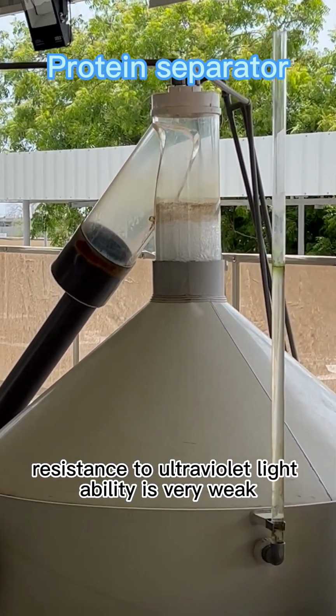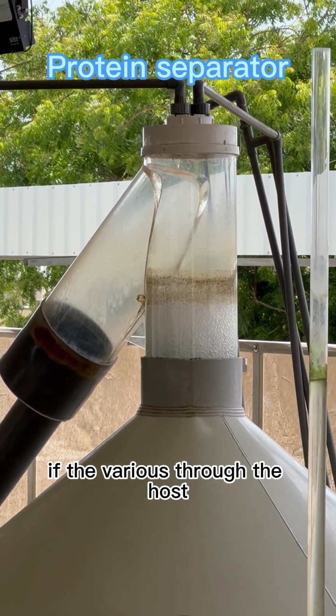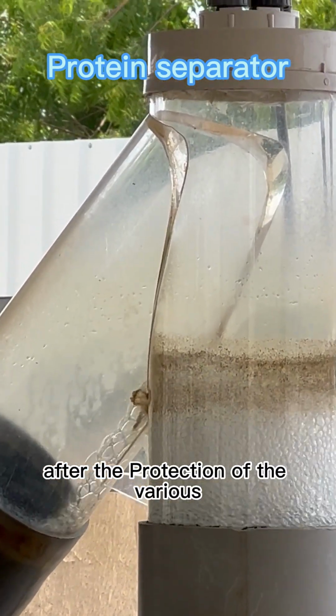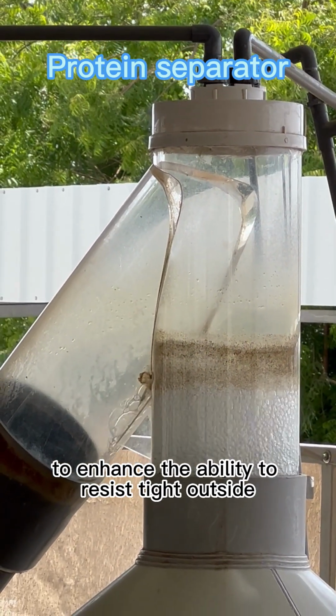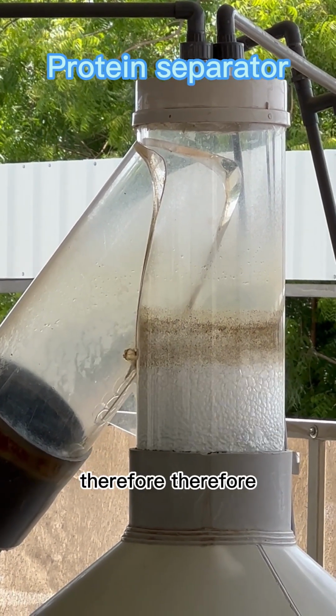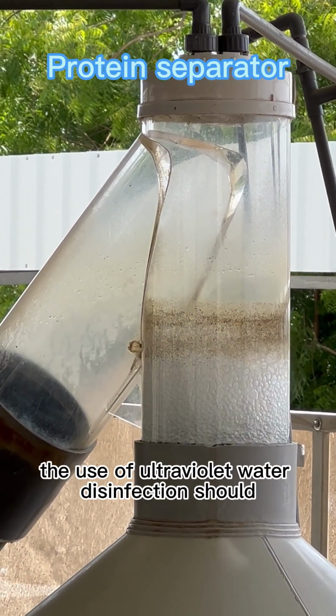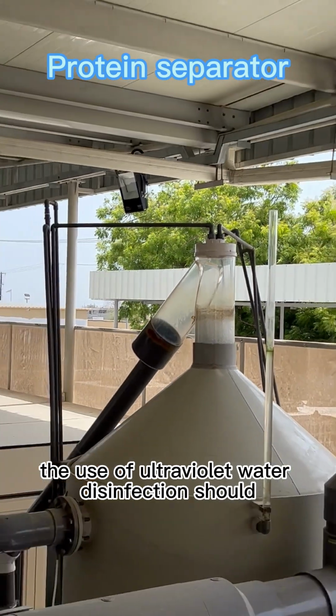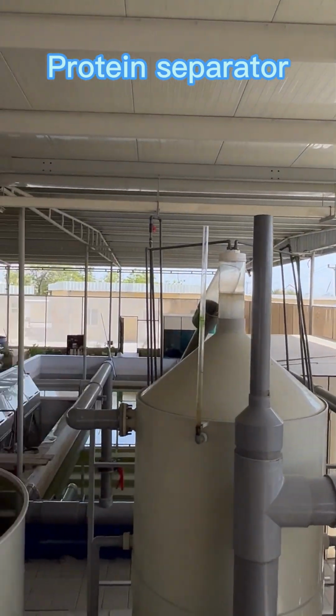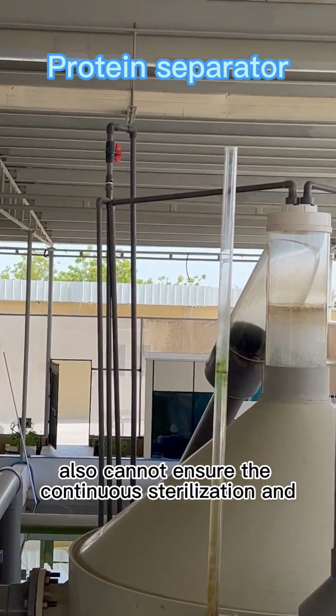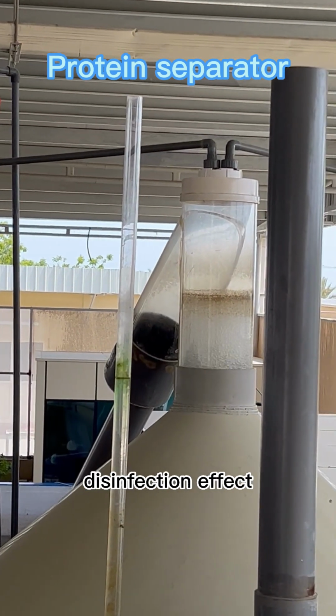The virus itself has very weak resistance to ultraviolet light, but if the virus passes through a host, the protection of the host enhances the virus's ability to resist the outside. Therefore, ultraviolet water disinfection should also be combined with pre-treatment, and it also cannot ensure a continuous sterilization and disinfection effect.